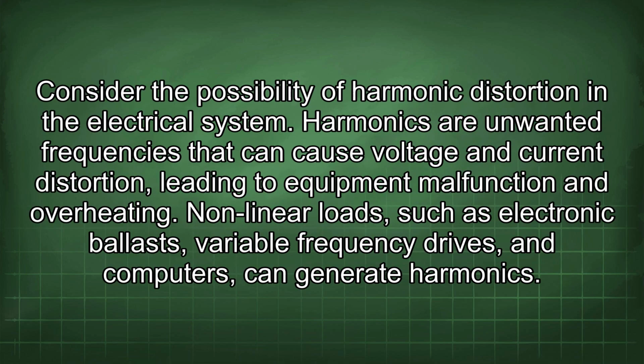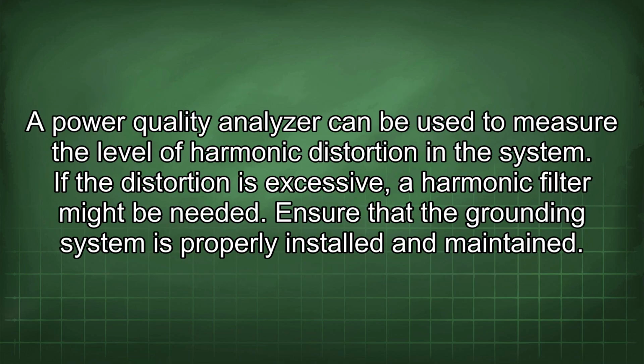Consider the possibility of harmonic distortion in the electrical system. Harmonics are unwanted frequencies that can cause voltage and current distortion, leading to equipment malfunction and overheating. Nonlinear loads, such as electronic ballasts, variable frequency drives, and computers, can generate harmonics. A power quality analyzer can be used to measure the level of harmonic distortion in the system. If the distortion is excessive, a harmonic filter might be needed.